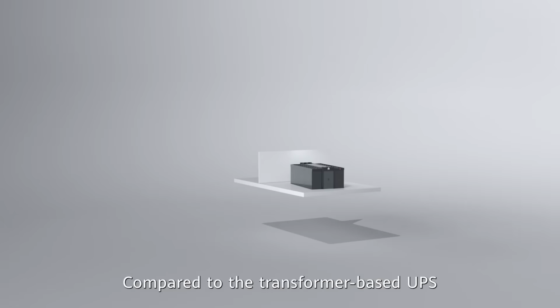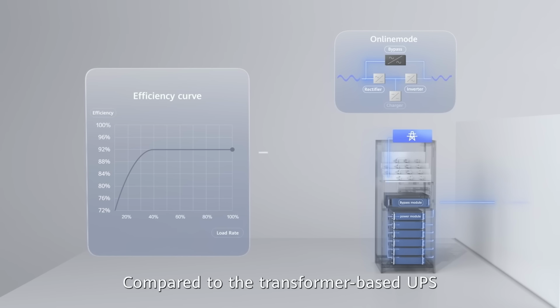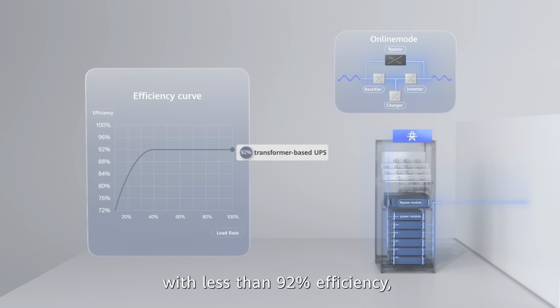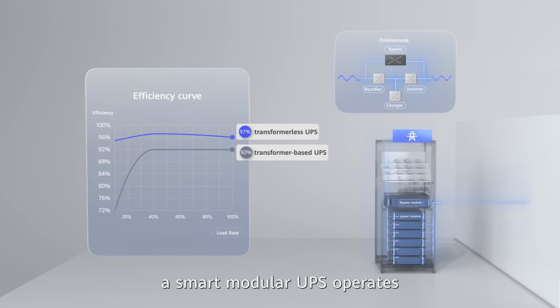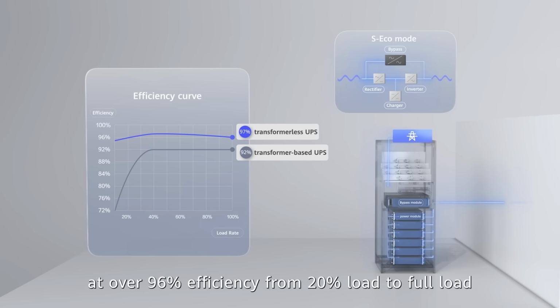warnings rapidly. Compared to the transformer-based uninterruptible power supply, with less than 92% efficiency, a smart modular uninterruptible power supply operates at over 96% efficiency, from 20% load to full load.